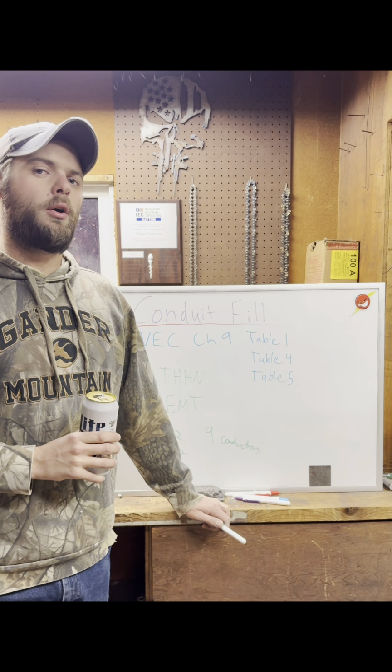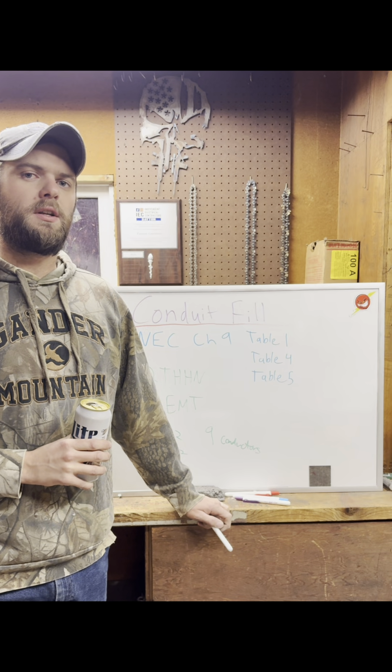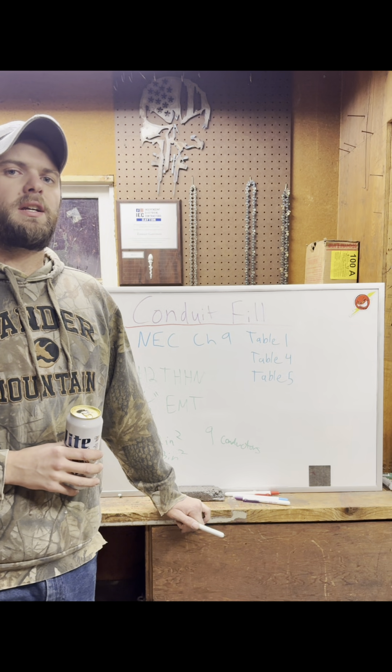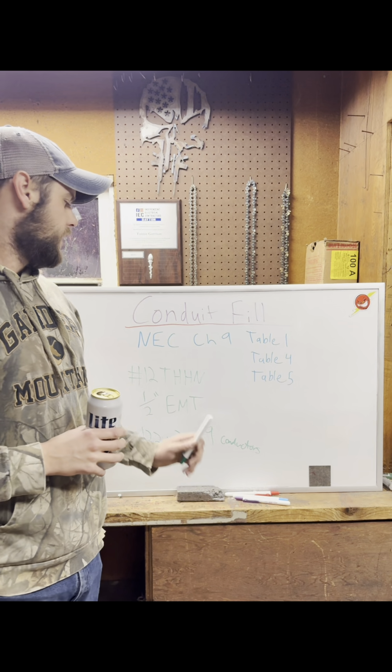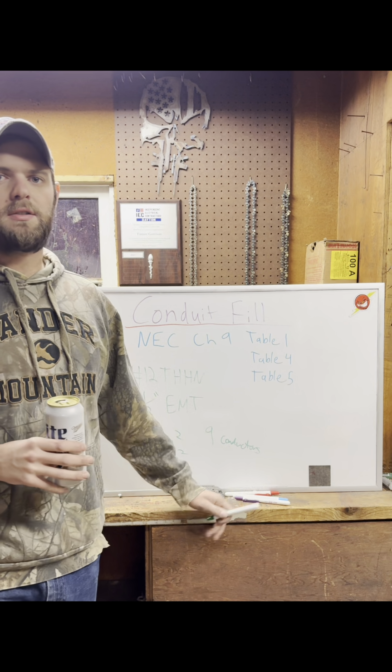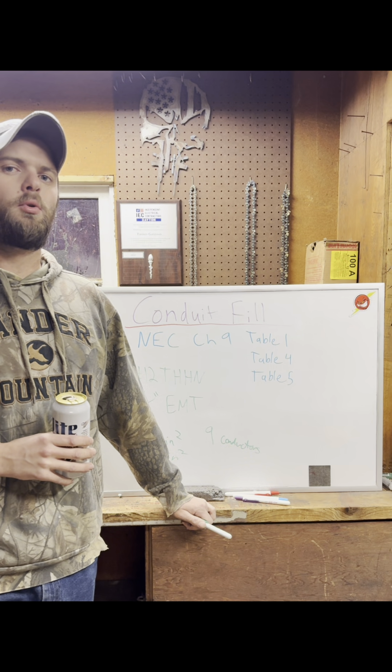Now, like I said, it's not always going to be 40%, and we'll talk about that in a later video. And yes, I know there's a cheat sheet in Annex C, but it's not always going to be that simple. If you get a question where there's different size wires, Annex C is not going to help you, so that's why it's important to learn how to do the math.